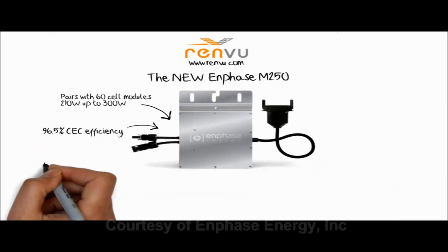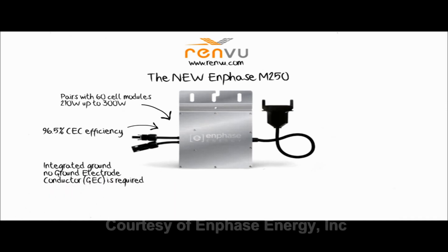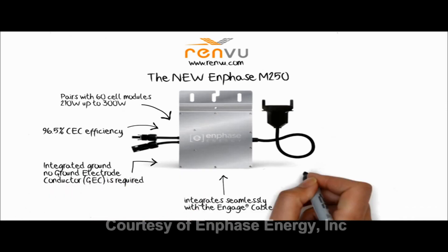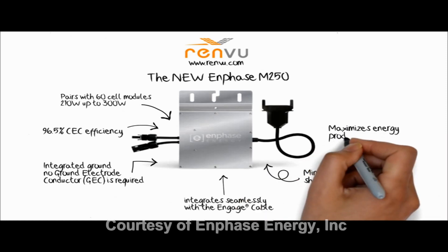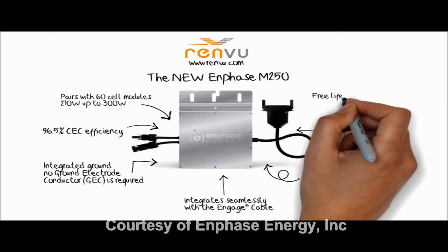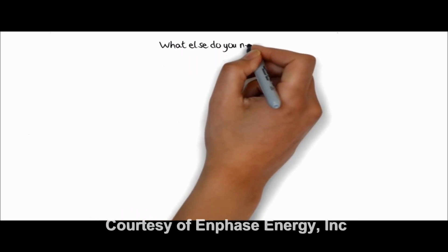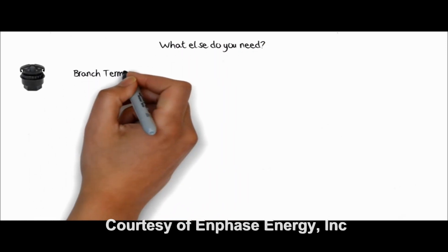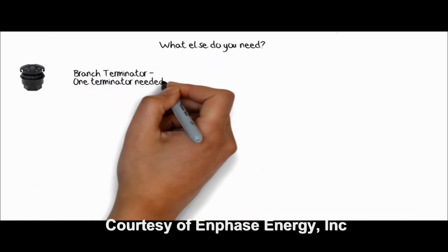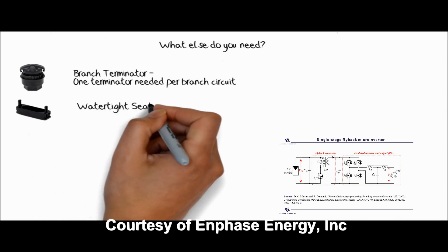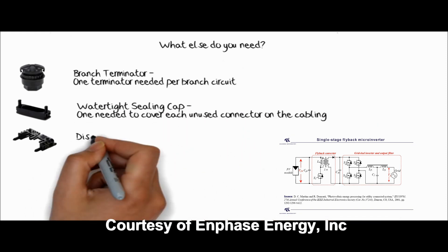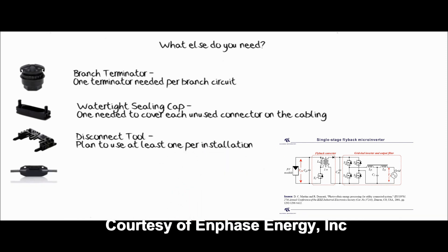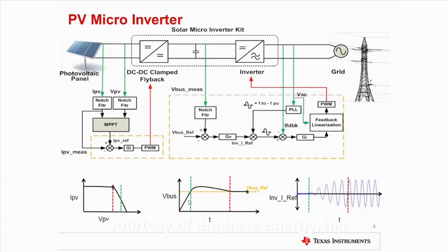Next, I will introduce a product, the M250 from Enphase. It has 60-cell modules and a very high efficiency. Besides, its ground has been integrated into the product. As shown in the topology of the product, it is clear that it has an interleaved network, which consists of two flyback converters in parallel to meet the power requirements.